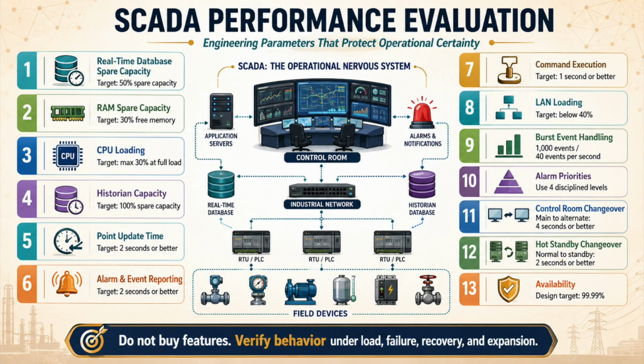A slow digital status is not equal to a fast analog value with scaling, alarming, historization, deadband, quality processing, display references, and operational consequence. So the correct question is not how many points the software can theoretically support, but how many points this delivered architecture can support while maintaining alarm reporting, screen updates, historian logging, command execution, redundancy synchronization, communication polling, CPU margin, RAM margin, disk performance, and network loading under peak and degraded conditions.